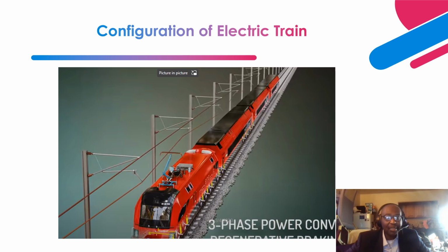Next is how this entire length of the catenary system looks. As you can see, the live conductor, the 25 kV line, is not straight but zigzag. There's a reason for that: it helps the two surfaces revolve around different contact points to prevent friction and corrosion from eating away the surfaces of the conductors. That's why it has that zigzag shape at different points.